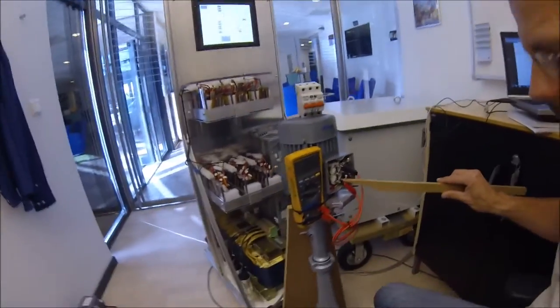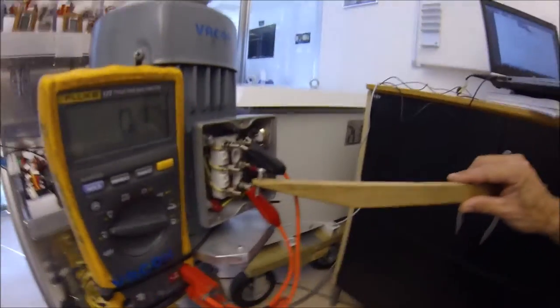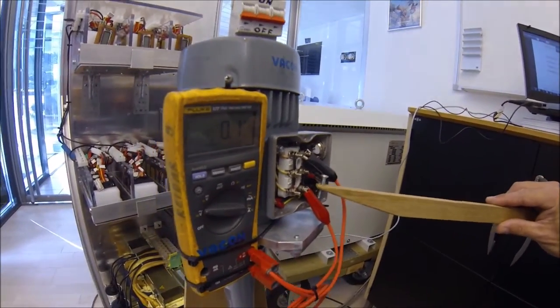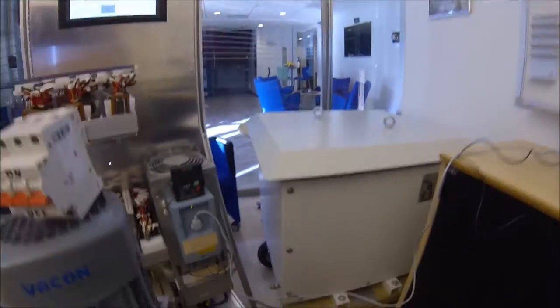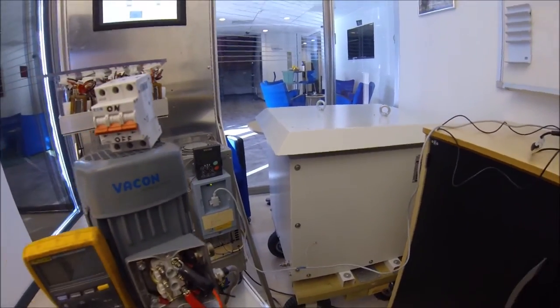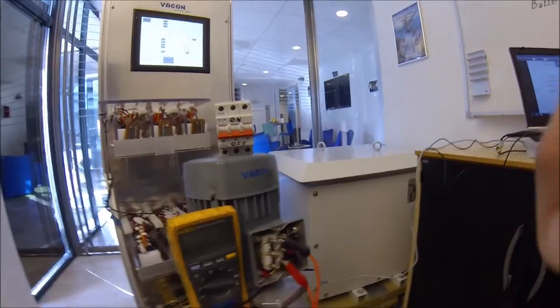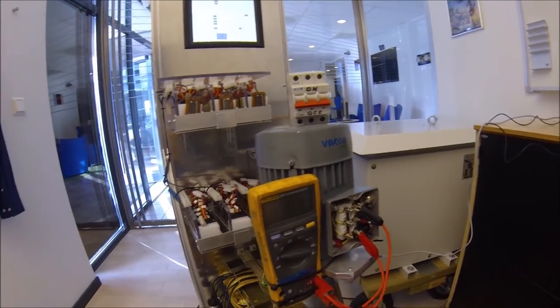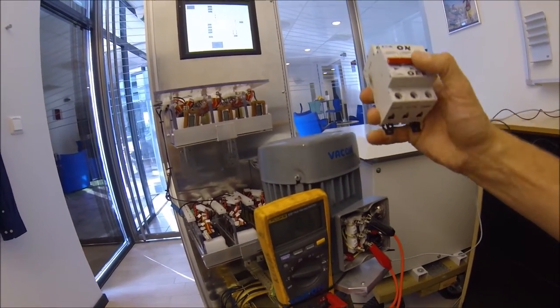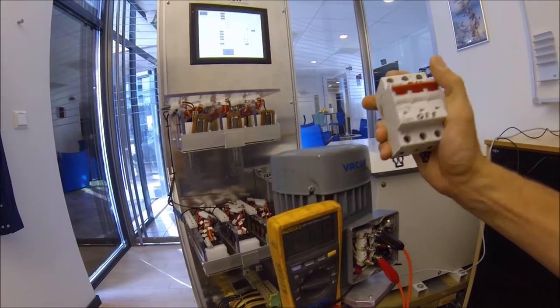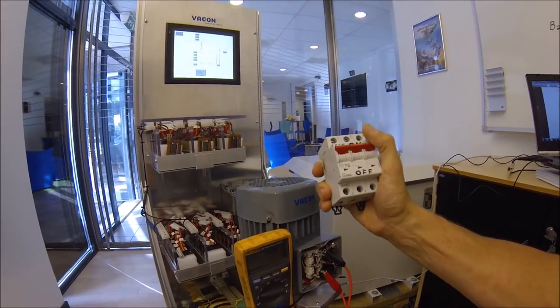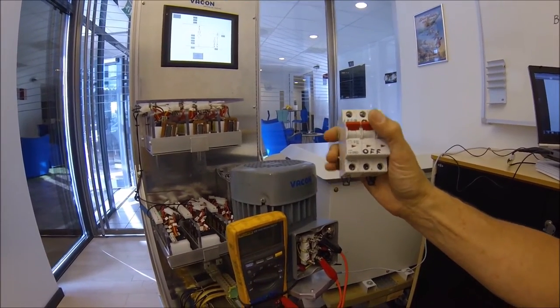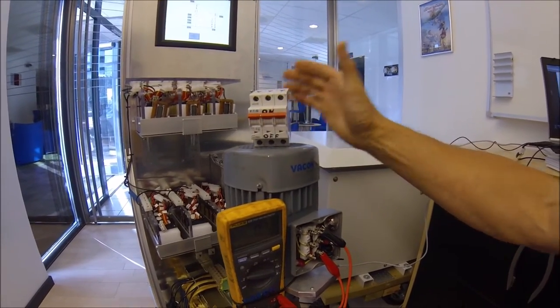We are now going to look into short circuit. If we short circuit the distribution, then there is a risk that a whole frequency converter will trip over current and then all the consumers will lose its power. We rather should want some of the fuses in the distribution system to trip and we want the drive to continue running supplying the other consumers.